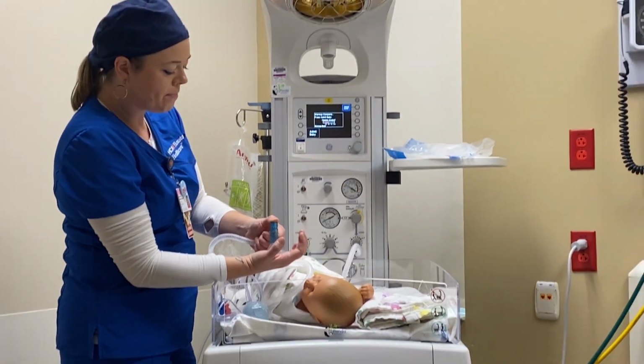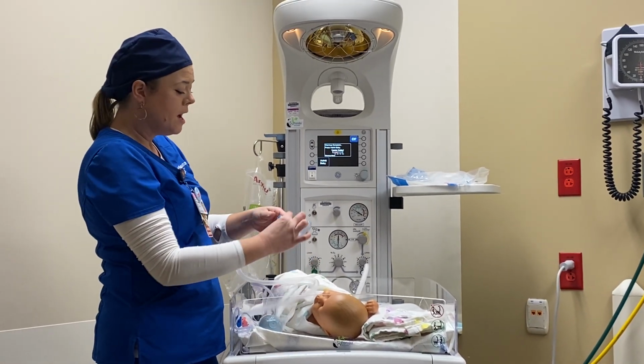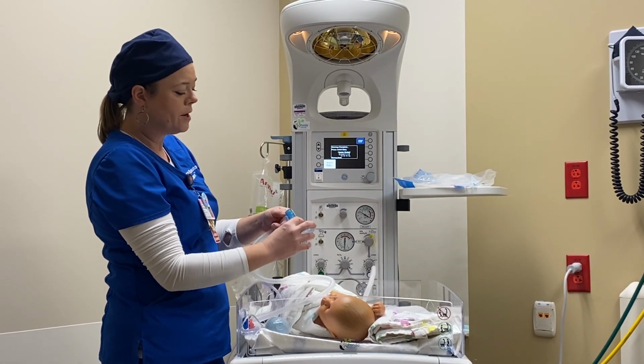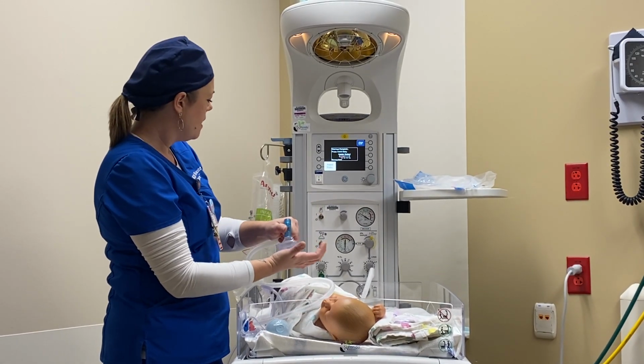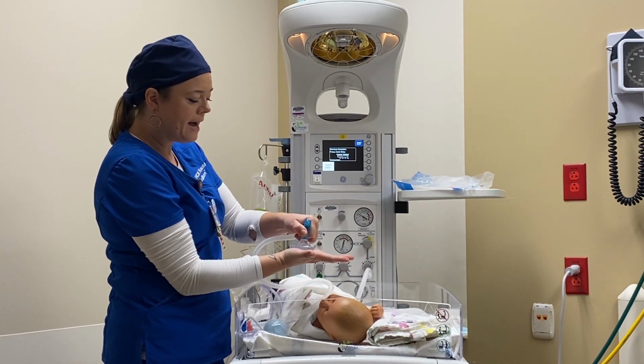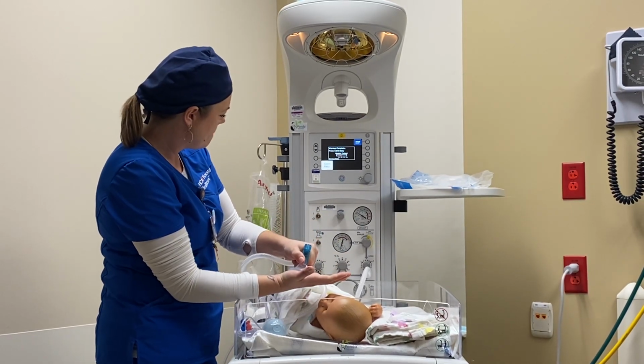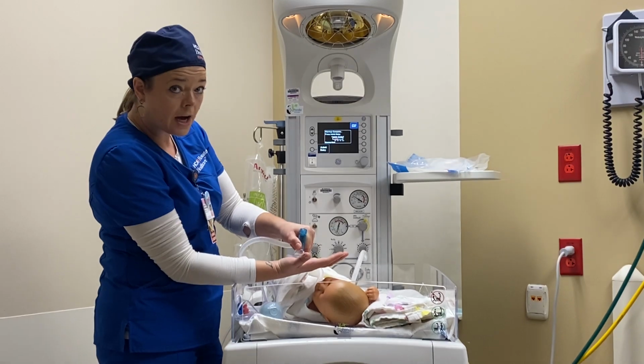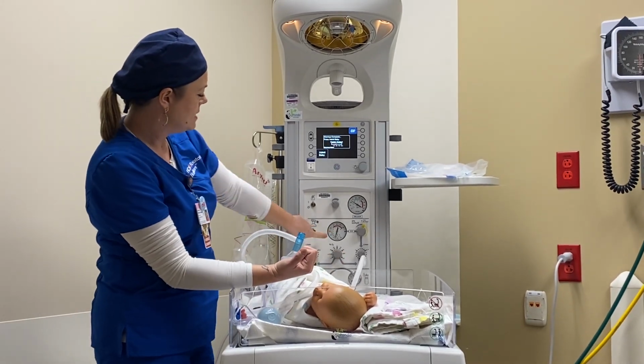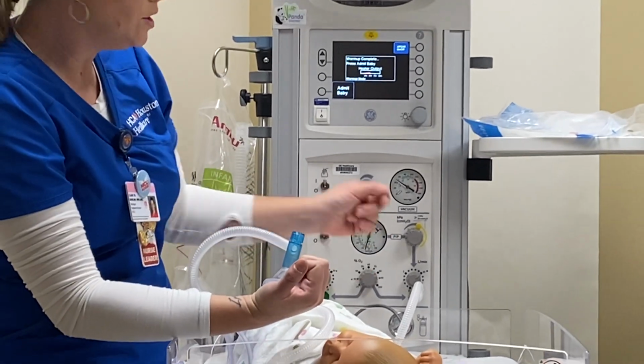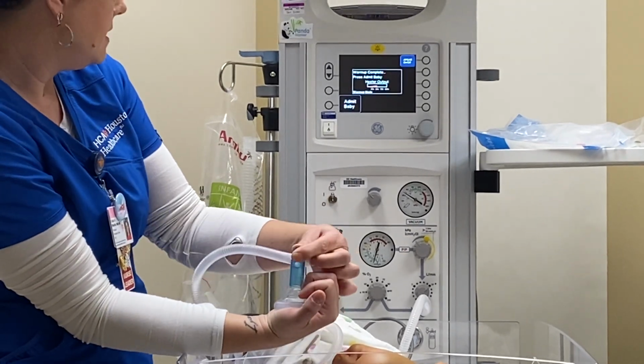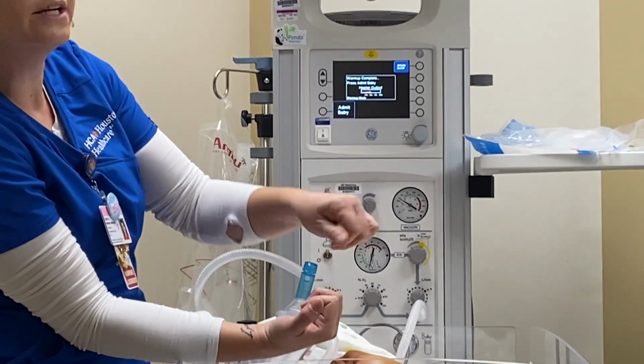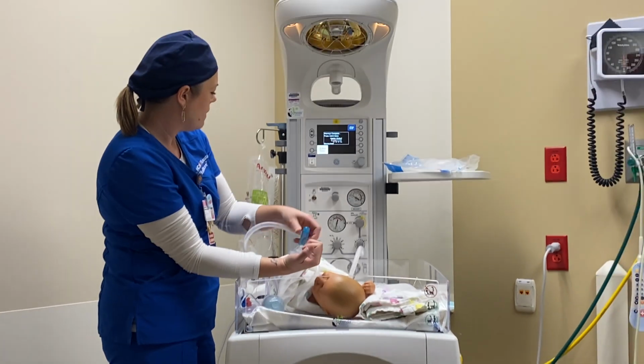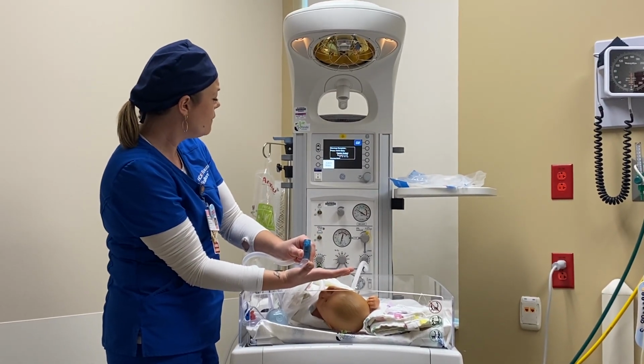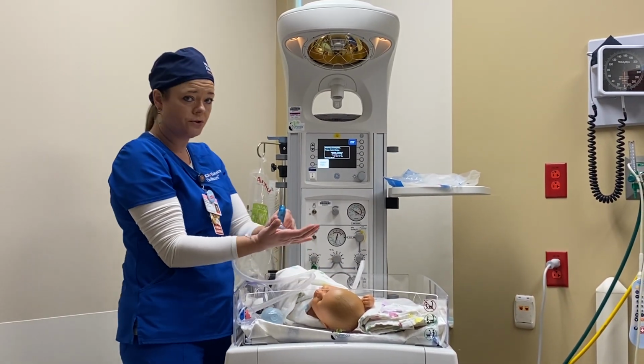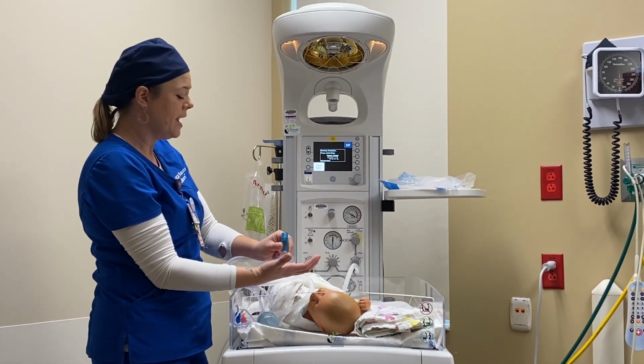So that is your PIP, and now you want to test your PEEP. You get your positive end expiratory pressure, so you test that by occluding on the mask, but not the top, okay? So if I'm occluding on the mask and not the top, I want my PEEP at 5. It is at 5 right now. You can adjust that by dialing this dial right here. And sometimes it takes a lot of turns to get where you need to go, but 5 is where you want it. If your baby requires more pressure than 20 over 5, you can do that.